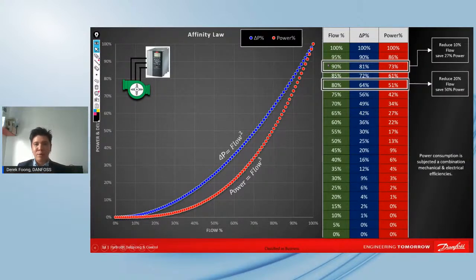So like I said, I would just like to pinpoint that if we save 10% flow rate, and this is proportional to flow squared, then we'll be saving about 19% differential pressure. Again, 20% flow rate would save about 36% differential pressure. Of course, power savings will be even more, as power is proportional to flow cubed. So this is a simplified equation right here, not to go too deep.